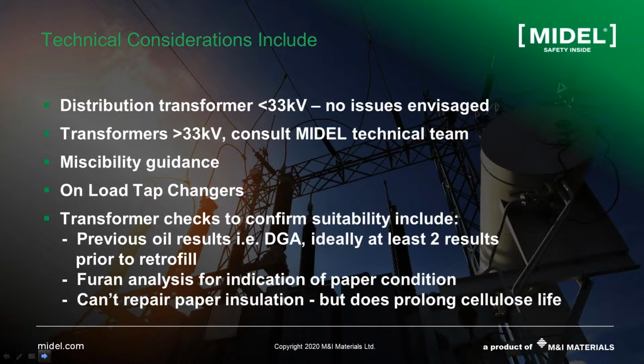However, if somebody would like to retrofill a silicone-filled transformer, we would say it's not the best option, because silicone liquid is not miscible either with ester liquids or mineral oil. If you try to do that, you will see some foaming effects, and we always like to avoid these kinds of things. So the point is that MIDEL ester liquids are miscible with mineral oil.